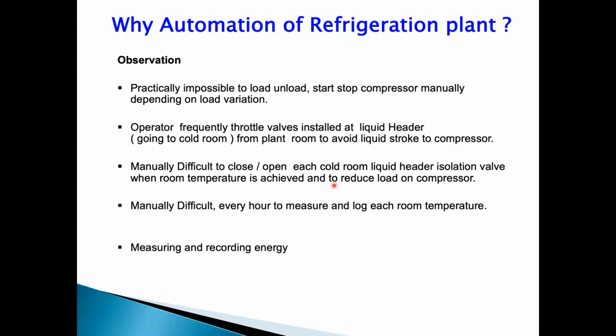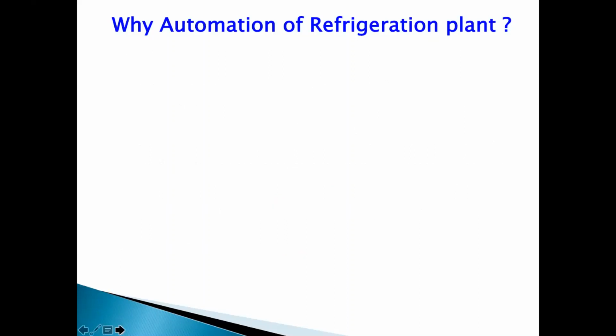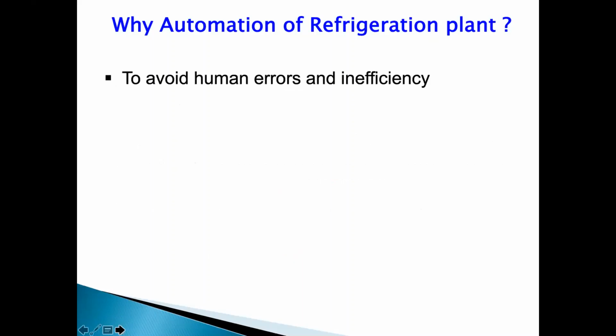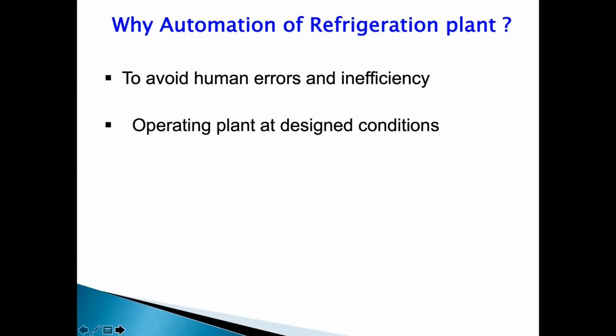And of course, as I told you, energy becomes very crucial and the cost of energy is becoming important. It is affecting the overall plant operation. And then what happens is when these plants become big and are operated and recorded by human beings, there are errors and inefficiencies. I've seen some plants where the operator used to throttle the valves on the receiver so that liquid feeding to the evaporator is less, and he would partially unload the compressor and sleep at night. So the plant runs continuously for a longer time, spends a lot of energy, doesn't get the results, and the owner pays the energy cost.